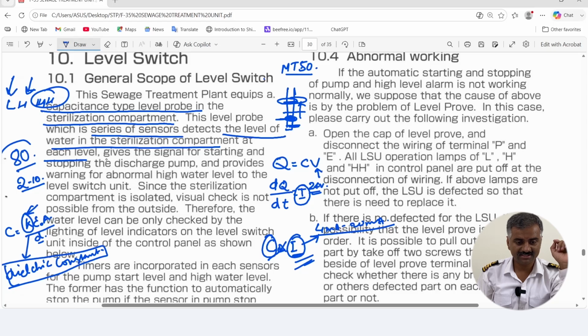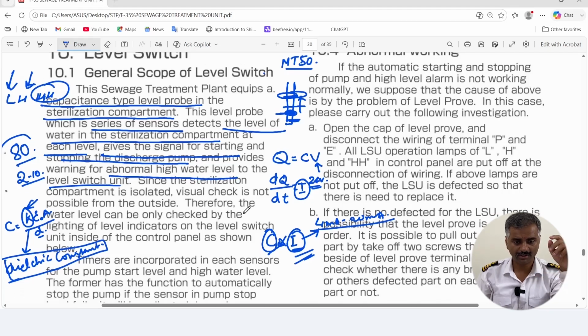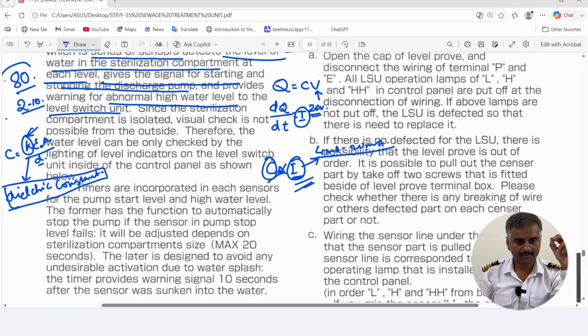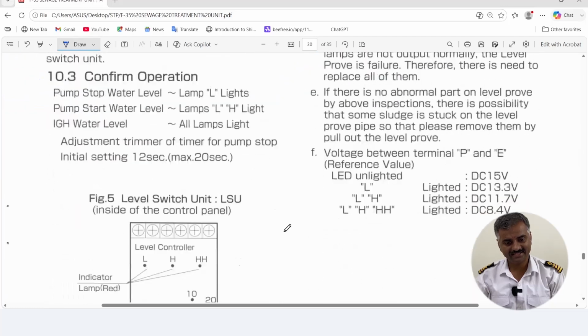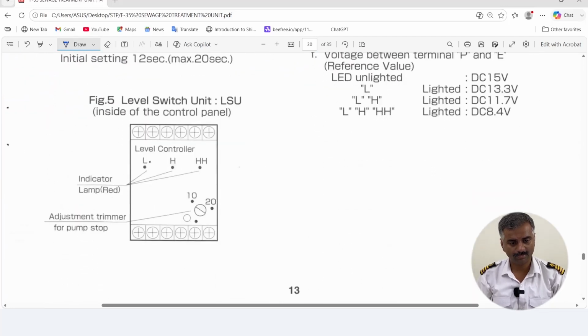So this gives the start signal and stop signal for the discharge pump, and gives you an abnormal high water level alarm, which we have already talked about. A visual check is not possible, so the water level can only be checked by the indicators. Where do you find these indicators? You find these indicators on the control panel. On the control panel, you have these three indicators: low indicator, high indicator, and high-high indicator, that are lamps. These are all three red lamps.